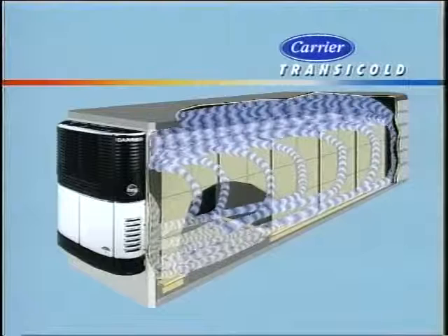Now check to see which mode the unit is operating in. Our unit is in continuous run from last trip. In this mode, the unit will run continuously, cycling between high speed and low speed and between heat and cool to hold box temperature at set point. Continuous run is generally used when hauling sensitive products such as produce. Continuous run operation provides continuous airflow inside the trailer and very close temperature control of the product.